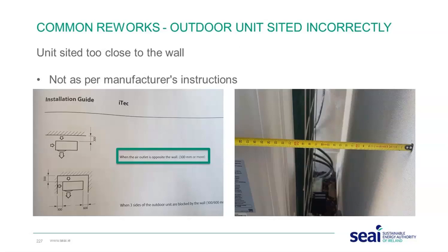So when an inspector's out on site, he will have a look at the manual and at what the manufacturer's guidelines are. He will check what the siting, distances and tolerance should be. So just on this example here, we have a copy of the manual. The inspector will open the manual. He'll see that the manufacturer recommends keeping it 300 millimeters away from the wall. That's to allow sufficient airflow through the system.